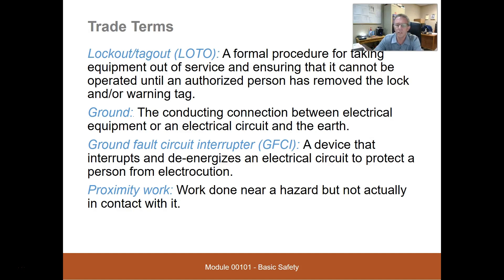A ground fault circuit interrupter, or GFCI, is a device that interrupts and de-energizes an electrical circuit to protect a person from electrocution. A GFCI is personnel protection. What it does is monitor the current in the circuit, and if there's a small imbalance, it turns off really fast.